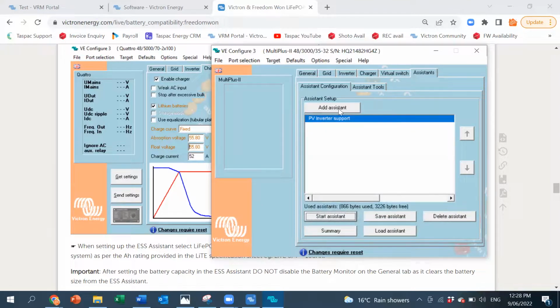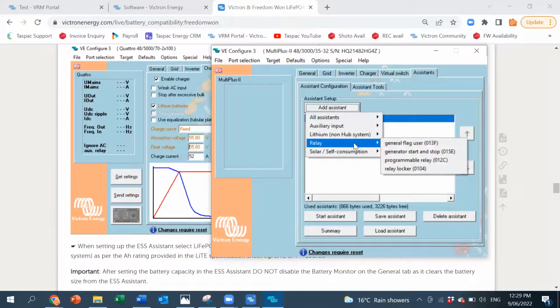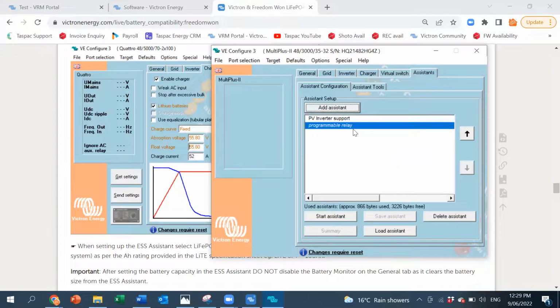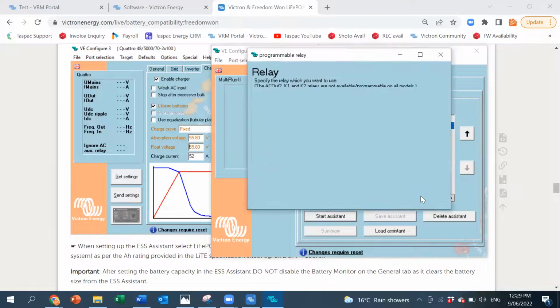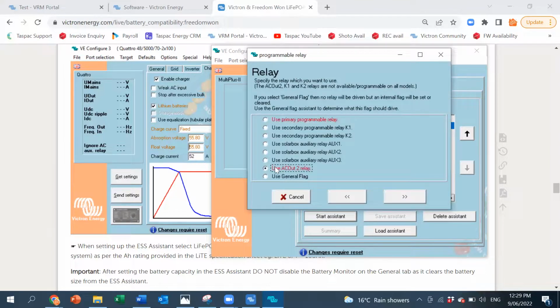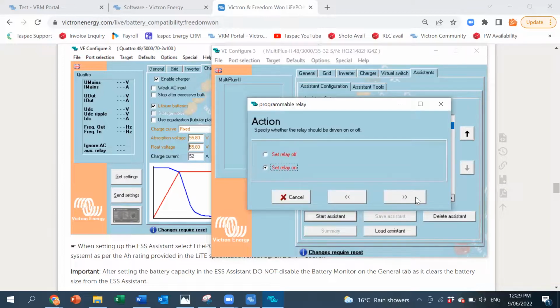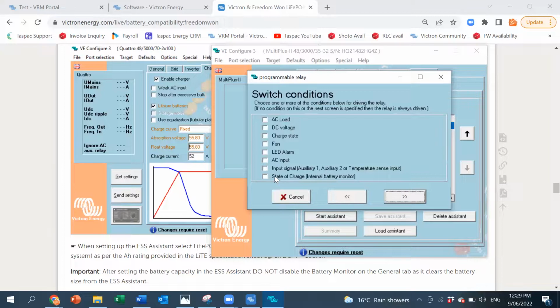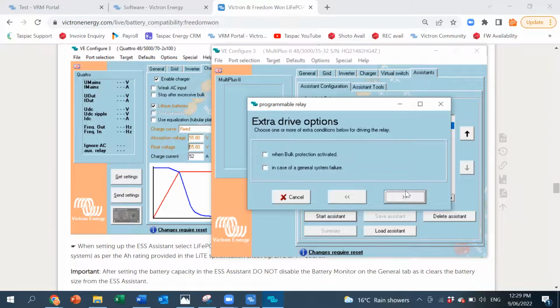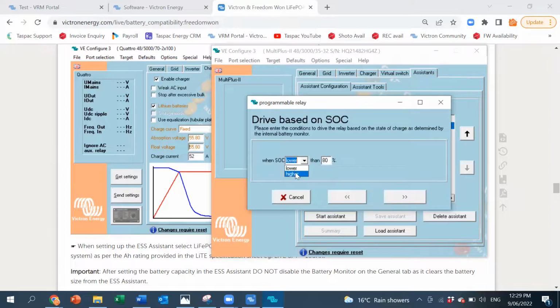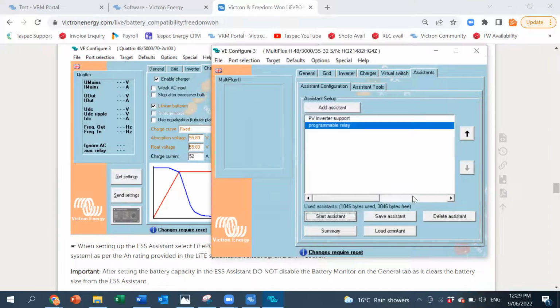And that's programmed. Now I'm going to add another assistant called a relay assistant. Programmable relay. Start that. What I'm going to do is tell the AC2 output, because there's two AC outputs, one's got a relay. I'll tell it to turn on when the batteries are at a state of charge that is higher than 98%. And that could be used to run a hot water cylinder element.